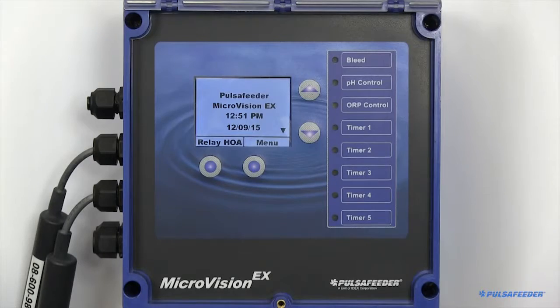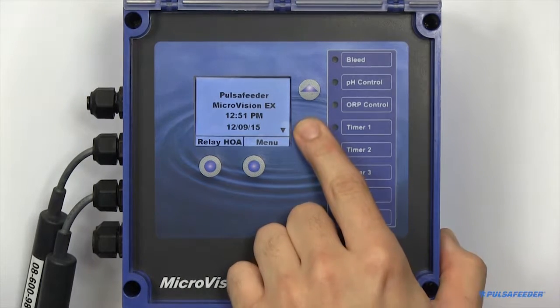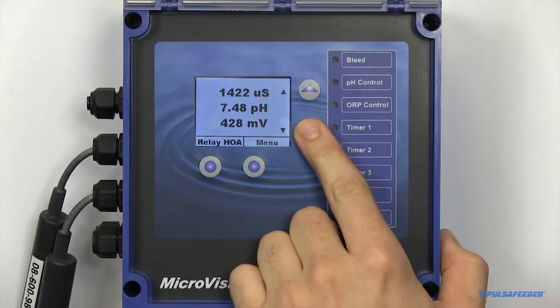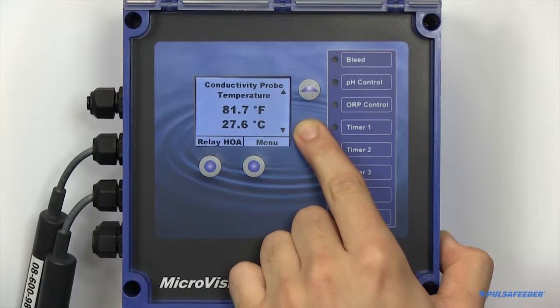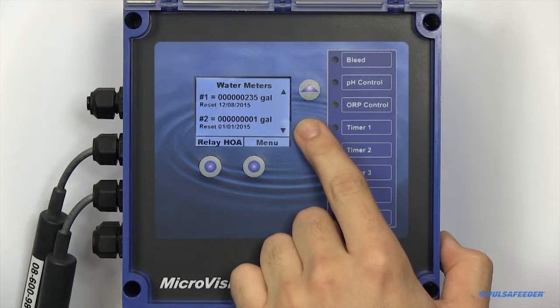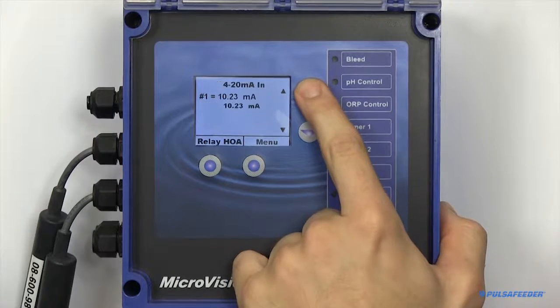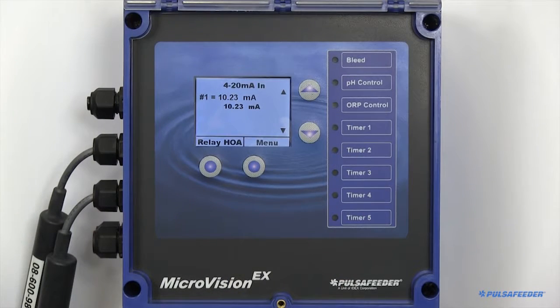Upon booting your MicroVision EX, you'll be welcomed by the home screen. Featured on the home screen will be the name of the unit, your date and time, any of your probe readings, the temperature, water meter readings, and any of the 4 to 20 milliamp in readings if they're enabled.